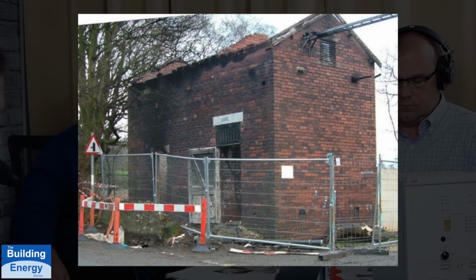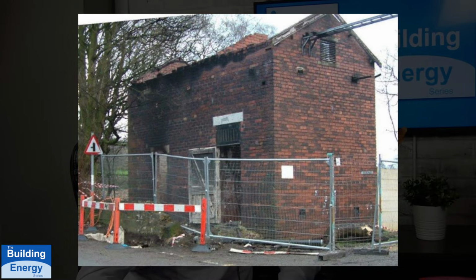That gives you an idea of the amount of pressure that's generated, not just in the switchgear cubicle, but in the electrical room. For example, you see the picture of that substation which has the roof completely blown off. Is that the third picture with the brick type building? Yes, that's right. So much pressure built up that it just blew out the top. Exactly. When you think about it, that roof would have landed somewhere. So it's obviously dangerous within the electrical room, but also in the exterior surroundings of the electrical room, it could be very, very dangerous.